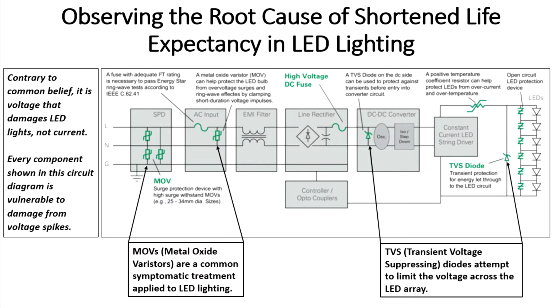If the voltage runs higher than it should be, the lamp won't last as long. If you get a voltage spike, you can take out a portion of the array of LED lights themselves, and you will not get that 10 to 22 year projected life. With the very first spike, you may see the lamp output drop by a certain percentage, 50% or 100%, based on the magnitude of the voltage spike.